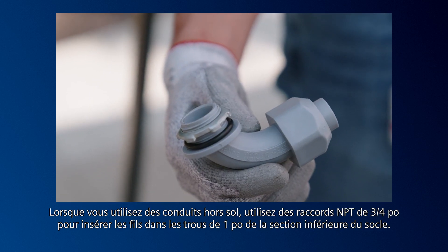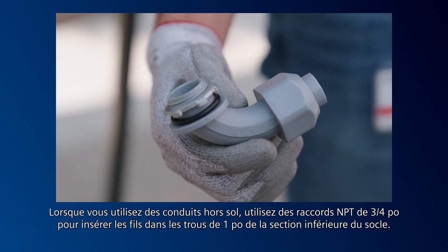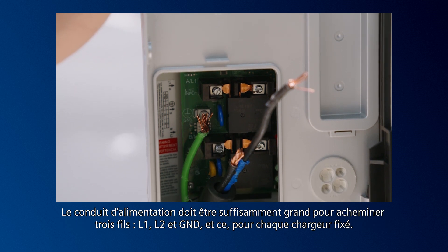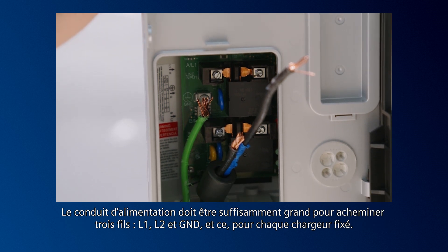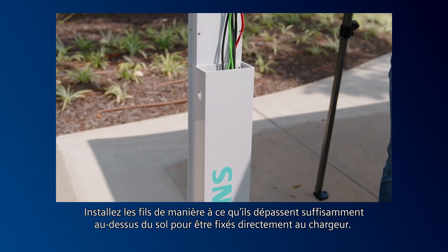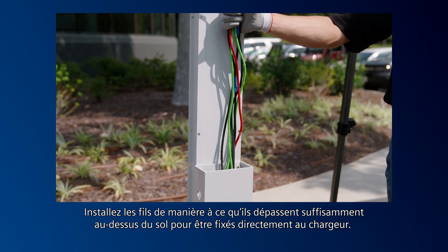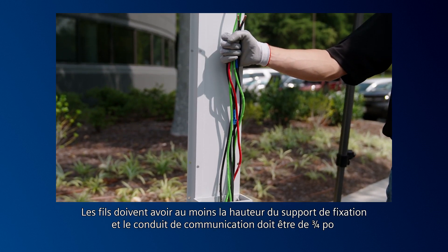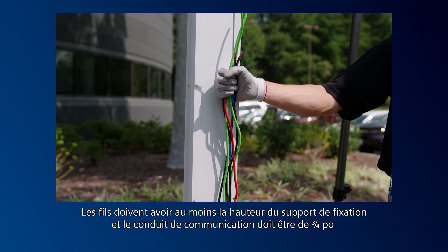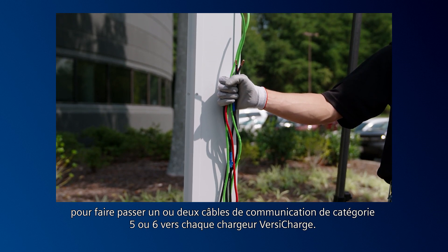When using above-ground conduits, use ¾-inch NPT fittings to enter through the 1-inch holes in the lower section of the pedestal. The power conduit should be sized to provide three wires—L1, L2, and GND—for each charger mounted. Install the wires so they extend far enough above the ground for direct attachment to the charger. The wires should at least be the height of the mounting bracket, and the communication conduit should be ¾-inch to run one or two Cat5 or Cat6 communication cables to each VersiCharge charger.